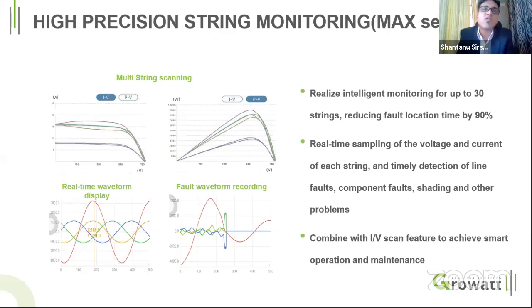For diagnosis, we provide waveform recording on both AC and DC sides for analysis purposes. Another interesting feature of the Max series is the triggering parameter: you can set a particular parameter, for example a voltage at 250 volts, and whenever the voltage crosses this threshold, the inverter automatically starts measuring values on the DC and AC side. This makes it very easy to analyze the inverter's performance at a particular level.